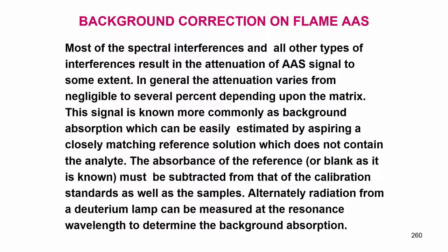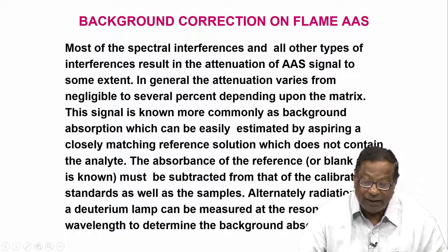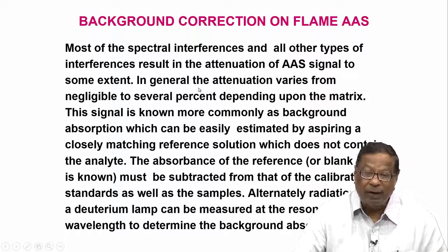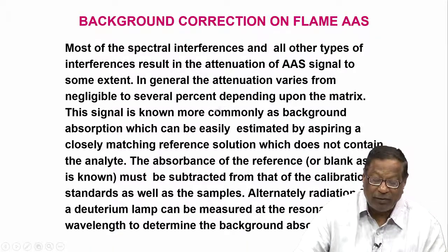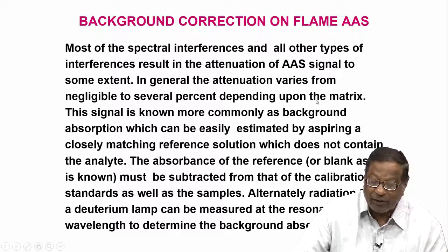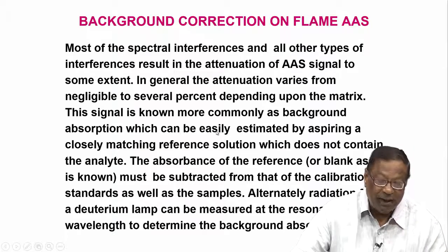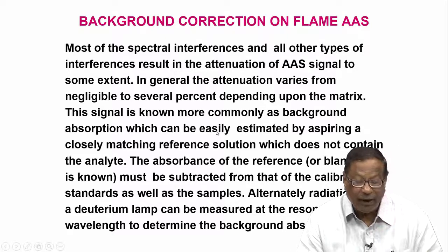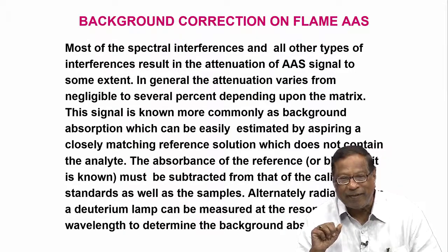In general, attenuation means reduction in the signal. This reduction in the signal varies from negligible levels to several percent — maybe 5 percent, 10 percent — and sometimes you may not even get a signal. It all depends upon the matrix elements. This signal is more commonly known as background absorption, which can be easily estimated by aspirating a closely matching reference solution that does not contain the analyte.